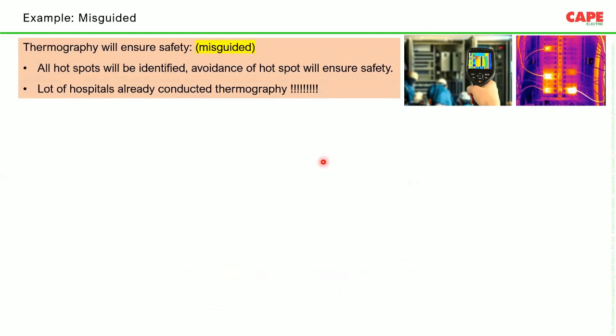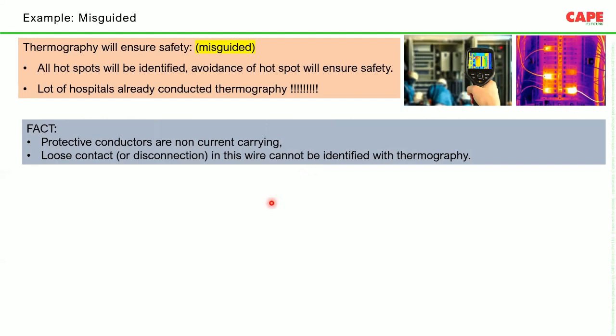People think that by doing thermography, complete electrical safety is made or possible. Actually, this is wrong. Thermography can, of course, tell you the hot spots. It can increase safety, but it doesn't mean that complete safety is achieved by doing only thermography. You have to do all the recommended safety measures as per IS 732. There are 18 inspection points and 10 testing points, plus additional testing for medical locations. Over and above, you can do thermography. If you do only thermography, please don't think that we will achieve safety.